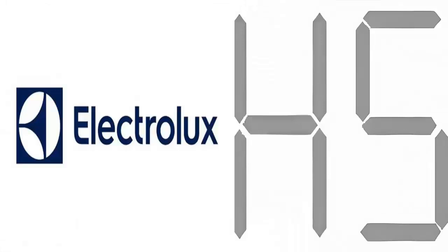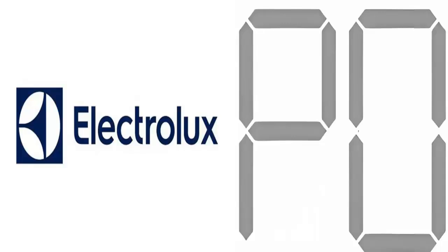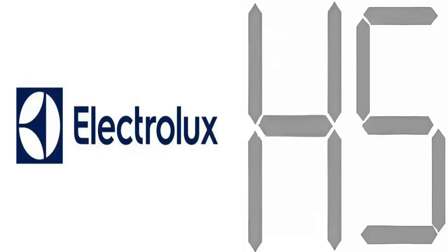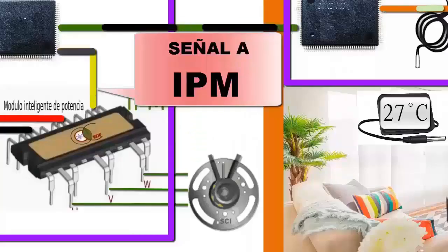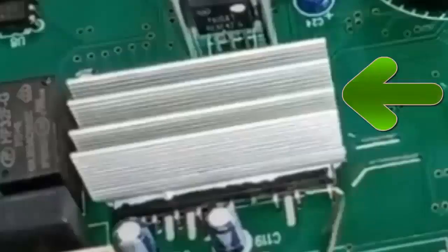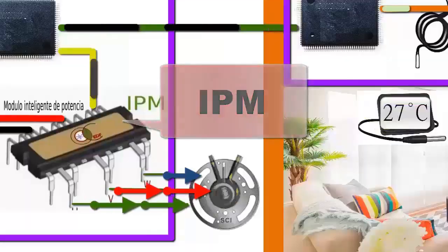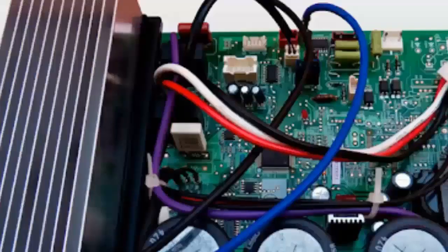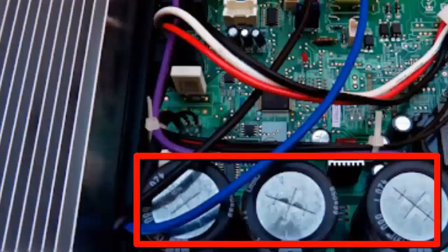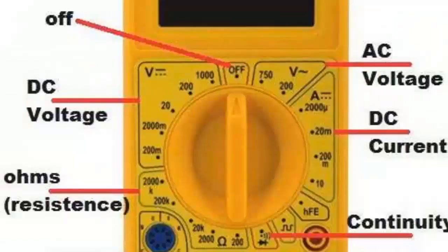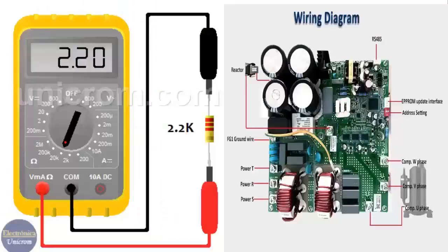Generally, the codes H5 and P0 in Electrolux units are generated when the inverter module protection, known as the IPM module, is activated. This code frequently appears when the IPM module's heat sink is loose and not making perfect contact, or when there are issues with the insulating paste or gel or the screw that secures the heat sink to the IPM module. Additionally, visually check the capacitors and the traces of the electronic module located in the external unit for abnormalities. Using a multimeter, measure the value of the electrical resistances near the IPM module.